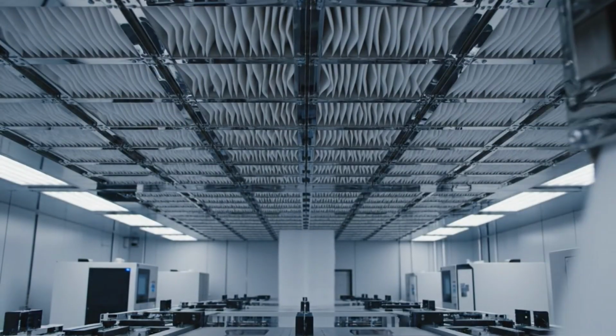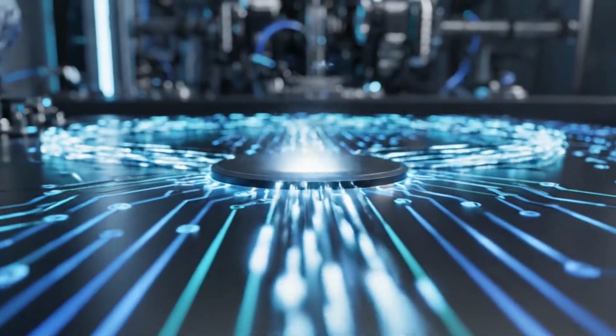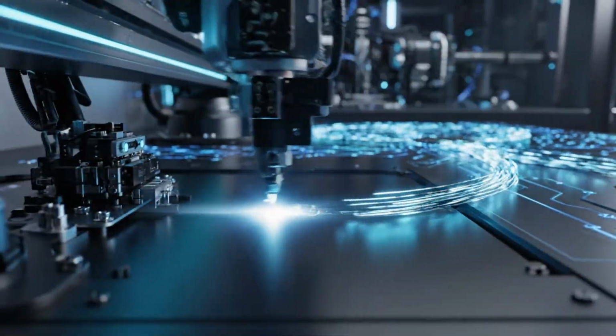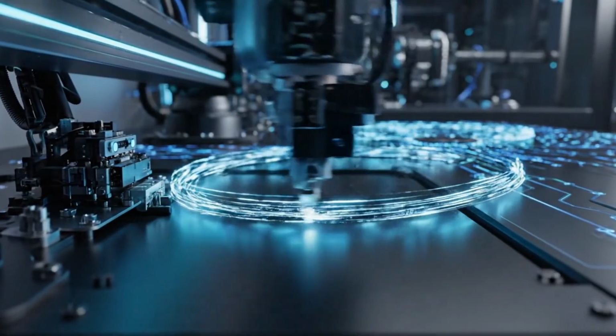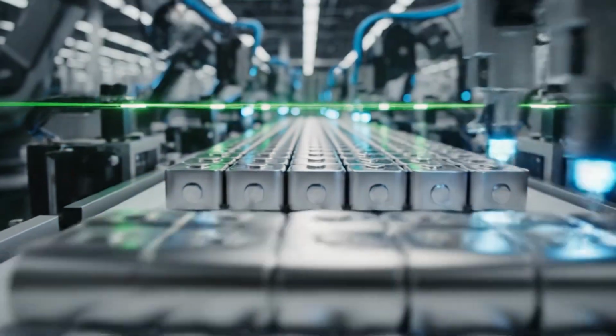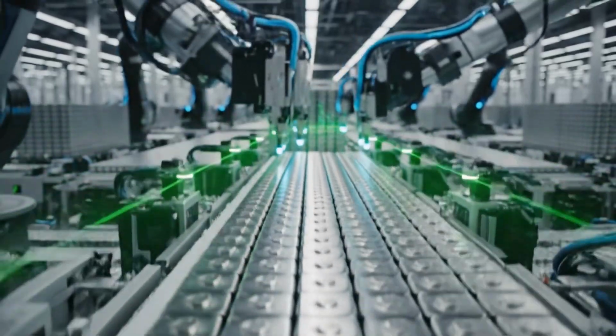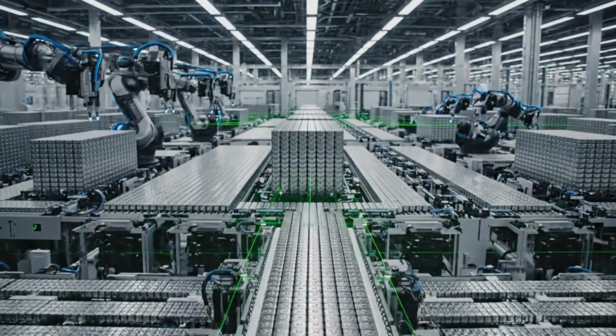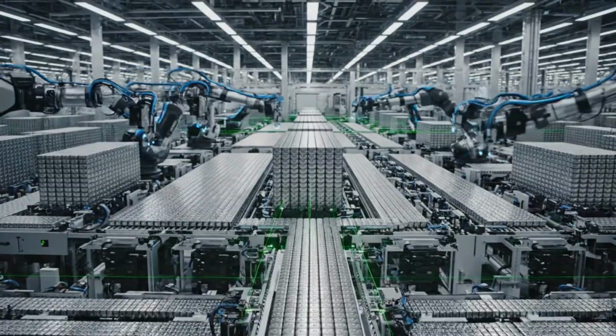Validation begins with electrical characterization. Each cell undergoes detailed measurement of capacity, internal resistance, voltage stability, and charge-discharge efficiency. These metrics establish a performance baseline that will be used throughout the battery's life. Cells that do not meet strict thresholds are removed immediately, preventing weak units from entering modules.